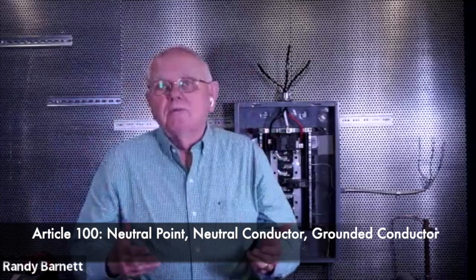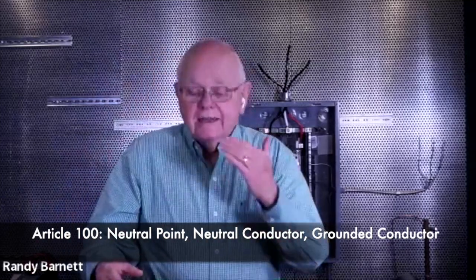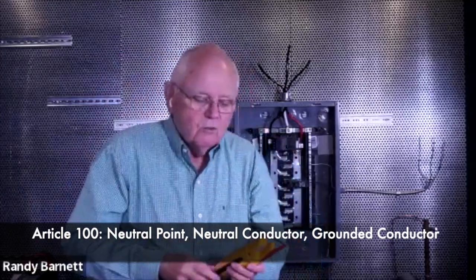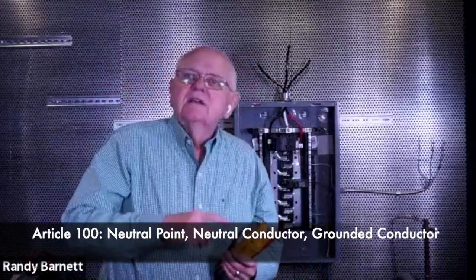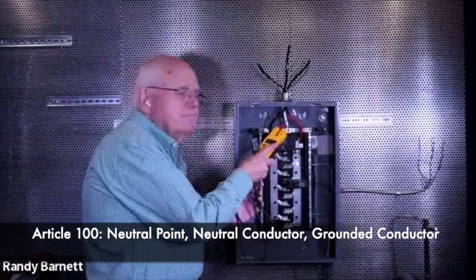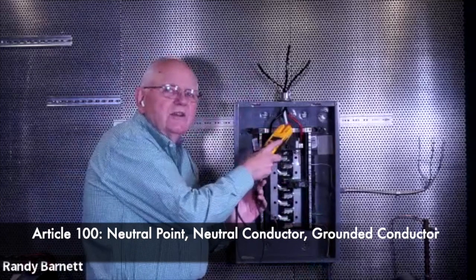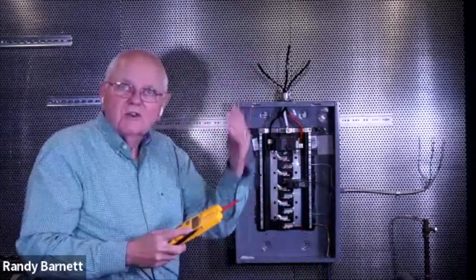And what do we mean by neutral? Well, we'd have to go to the code book, Article 100, and look up neutral point and neutral conductor. And yes, we'll find out it is a neutral. Why? Because this tap is in the midpoint between each end, the black and red ends of that single phase transformer out on the pole or on the ground, wherever it is, pad mounted, whatever.